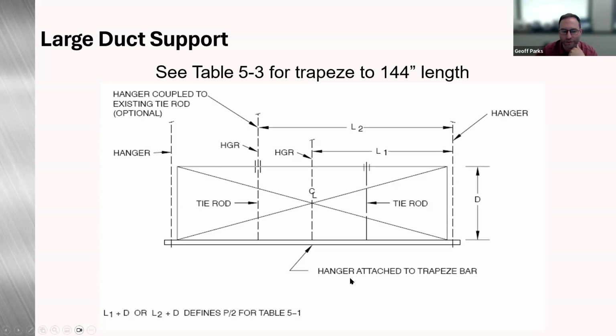But what you can do, within the standard, is use this figure, figure 5-7. And what it's saying is, hey, we can redefine how to size that trapeze based on a few things. So we have an L1 here and we have an L2 here. That means we're going to add a third hanger, and that's either going to be at the midpoint through the ductwork, or another option is for the L2 to tie into one of the tie rods within that ductwork. So I'm going to go through a couple examples on how to size not only the trapeze, but also your hanger for large ductwork, staying within the HVAC duct construction standard.